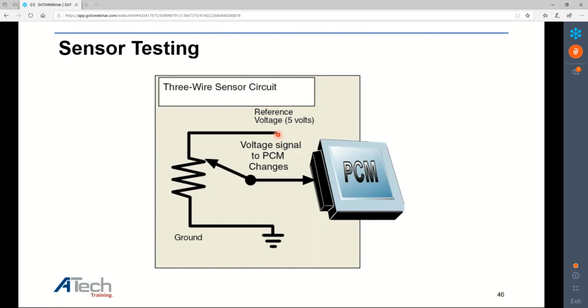A lot of times, if you have voltage problems on the input or the ground, that will definitely mess up the signal going back to the computer. If I'm missing 5 volts, it's going to mess up the voltage going back to the computer. So these are things you need to take into account in your process. A lot of times, I've seen people replace sensors when there's nothing wrong with it - it's just a bad ground wire.